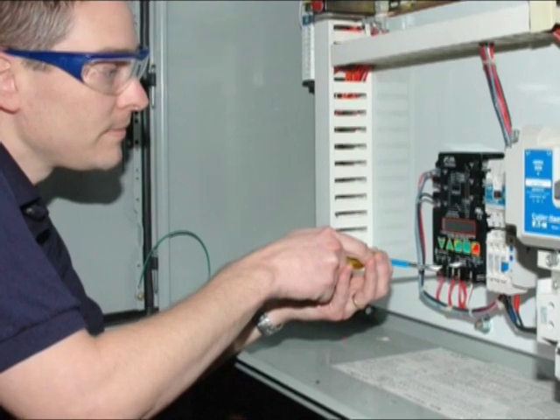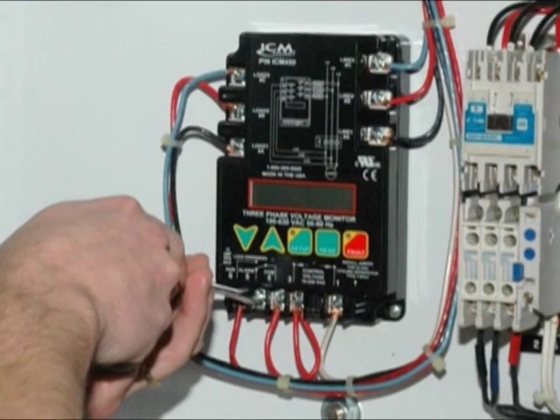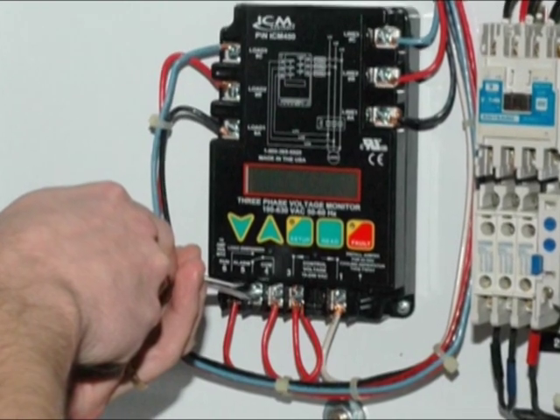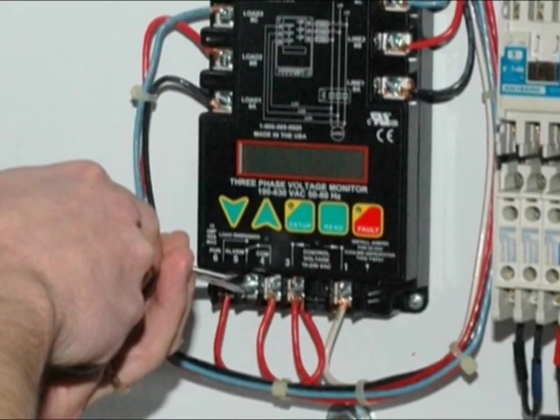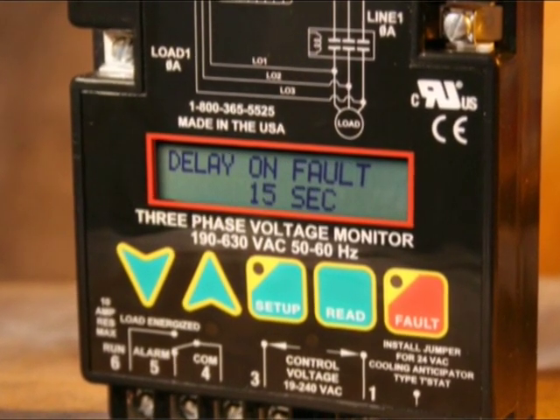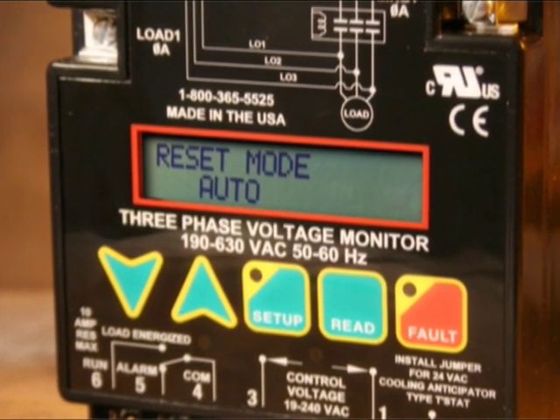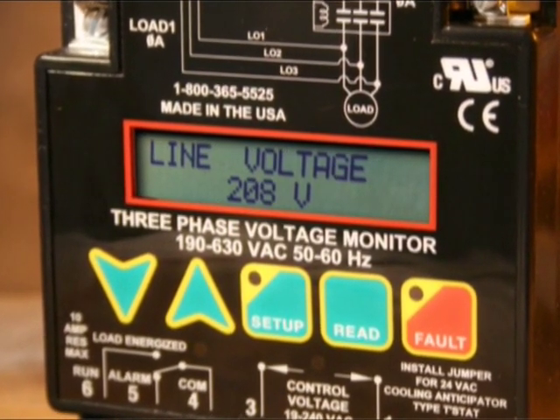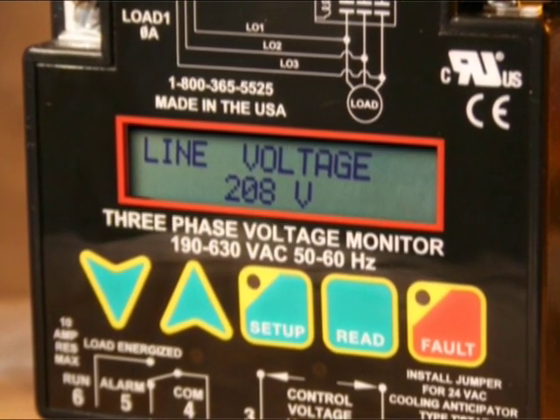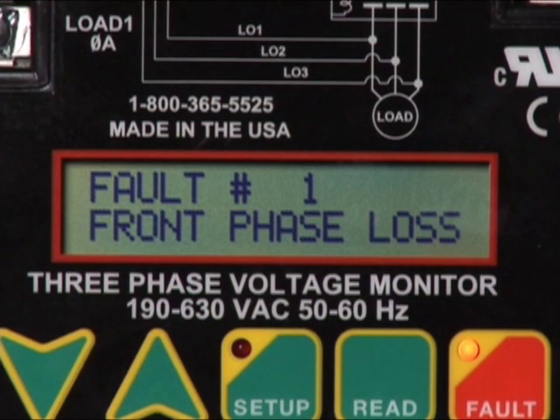ICM 450 motor protection is easy to install. Just mount it right inside the control cabinet, run connections to the line side and load side power lines, and connect the control circuit. The reliable high-temperature LCD display simplifies system setup. It takes just seven easy push-button steps to program the line voltage, maximum allowable voltage imbalance, under/over percentage, and more. The display can also scroll through the last 25 fault events, a big help when troubleshooting an elusive problem.